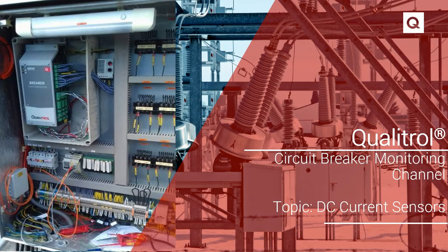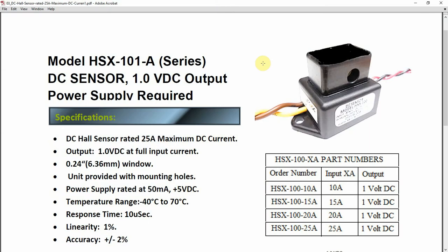This time's topic is DC current sensors. For DC current measurement, special sensors called Hall effect sensors have to be used. These sensors have 0 to 1 volt DC output and require a power supply. The sensor looks like this. It is a fixed core sensor with about a 1/4 inch orifice through it.